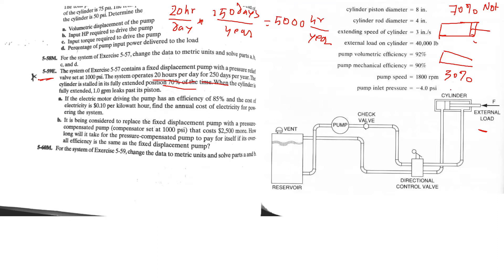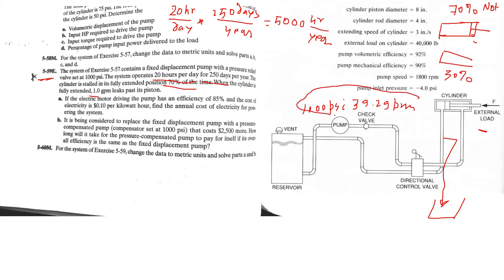When it's not working, the cylinder — because of the high pressure — leaks about one gallon per minute. There is also a pressure relief valve, so when the cylinder is stalled it basically dumps all the fluid to the reservoir. The pump is still producing 1,000 psi because the pressure relief valve is set to 1,000 psi, and the flow was calculated previously as 39.2 gallons per minute. So it is producing 39.2 gal/min at 1,000 psi and dumping it all back to the reservoir.